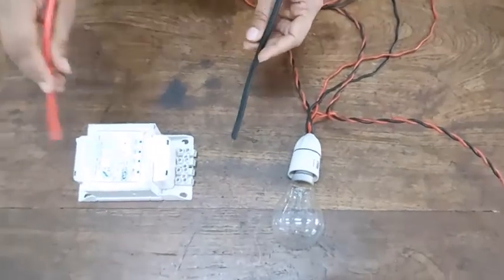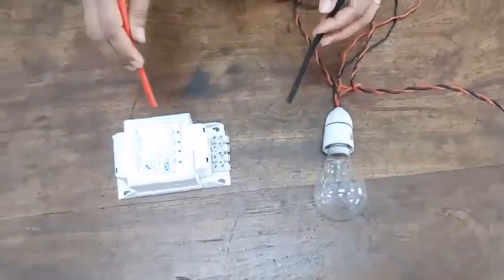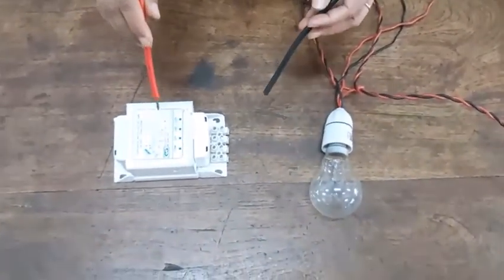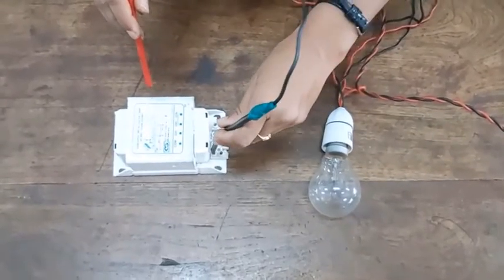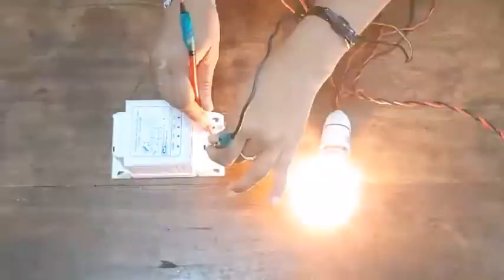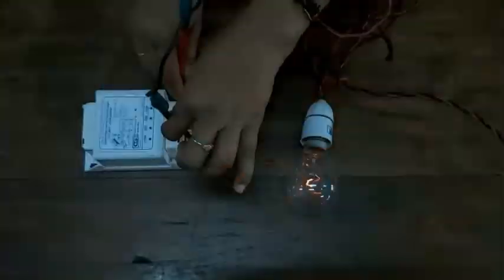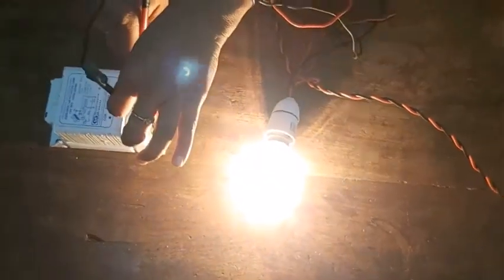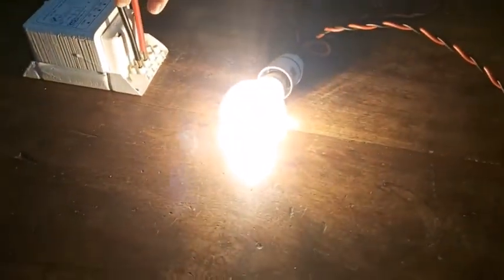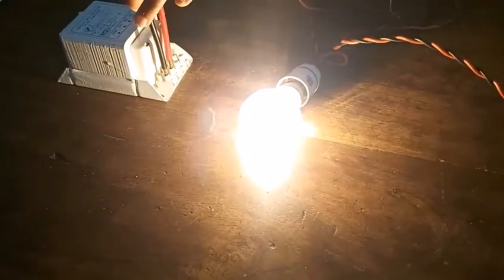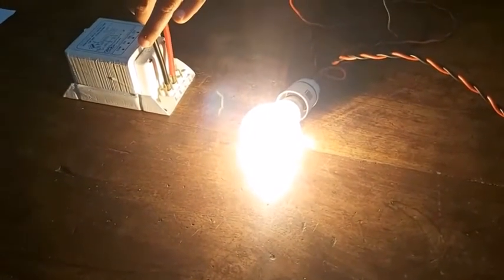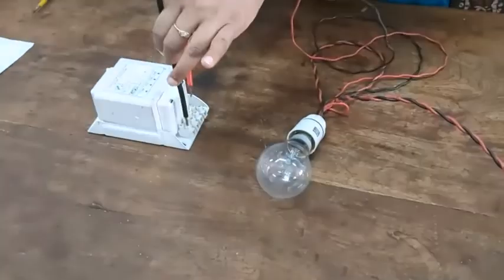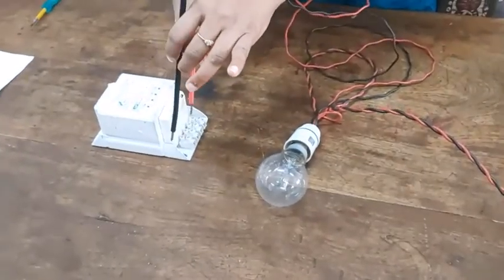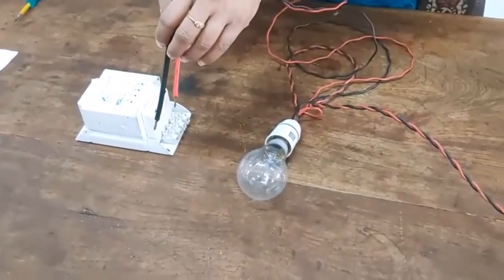Now I am going to do the short circuit and open circuit test for this choke. Here the series test lamp is dim. This shows that this choke is in working condition. If the series test lamp is off, we say that there is an open circuit in the choke or ballast.